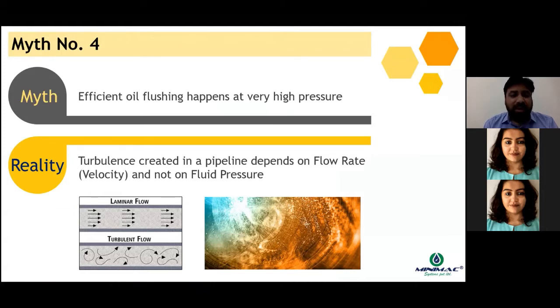We would see how turbulence is important for flushing and how turbulence is related only to the flow rate and not to the fluid pressure. It's important to generate a turbulent flow in the internals of the pipings and the cavities which have to be flushed. And thereby we need to create velocity and not pressure for performing oil flushing activity.